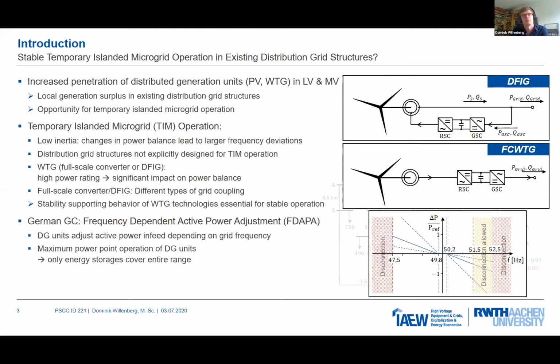To maintain a stable operation, for example, in Germany, in normal or grid parallel operation, distributed generation units are obliged to support the grid frequency. This is done by the so-called frequency dependent active power adjustment, or in the following FDAPA, whereas the DG units have to adjust the active power they feed in depending on the grid frequency.